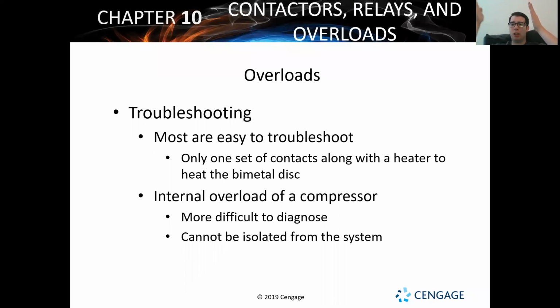And it's got a long path from that breaker panel to our outdoor unit. It's going to be going through fuses, it's going to go through disconnects, it's going to go through overloads, all right? When we're troubleshooting, what we're going to look for is, okay, well, my motor's not coming on. Well, first thing you want to check for, power. Is power getting to your motor? And if you don't have power at your motor, then you're going to start looking at that path from where the power started and where along the way it got lost.